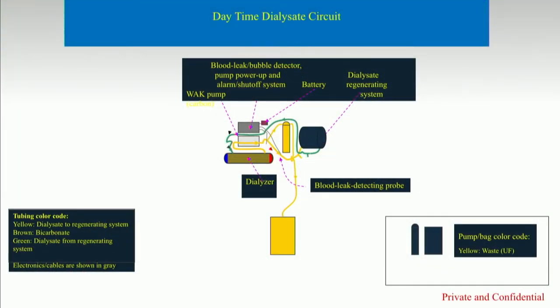And here is the day dialysate circuit, the daily module. The daily module has the same blood circuit, but the dialysate has only one cartridge to regenerate the dialysate.